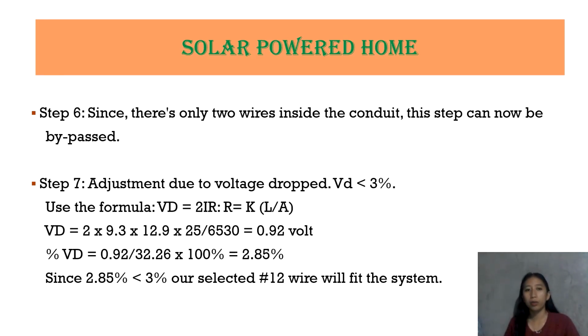Okay, so in our step 6, since there are only 2 wires inside the conduit, this step can now be passed. Okay, so sa step 7 naman, adjustment due to voltage drop, VD is less than 3%. So we are going to use the formula VD is equal to 2IR, R is equal to K, open parenthesis, L over A. VD is equal to 2 times 9.3 times 12.9 times 25 over 6,530, which is equal to 0.92 volts.